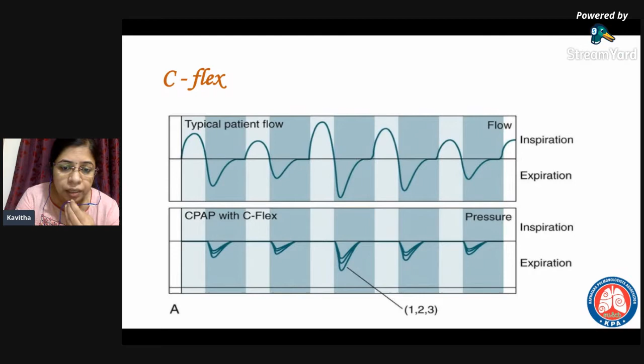Every patient is diagnosed with OSA and prescribed auto CPAP so that it adjusts the pressure on its own. So as the name itself says, it is auto titrating. You don't have to titrate. You can set a range. I can set a minimum PAP and a maximum PAP, and the device will vary the pressure throughout the night based on the patient's requirement. So the pressure changes until adequate patency of the airway is attained. So the pressure goes on increasing till the airway patency is maintained, and then it again starts decreasing till it identifies airway obstruction again. So the pressure will keep varying throughout the night.